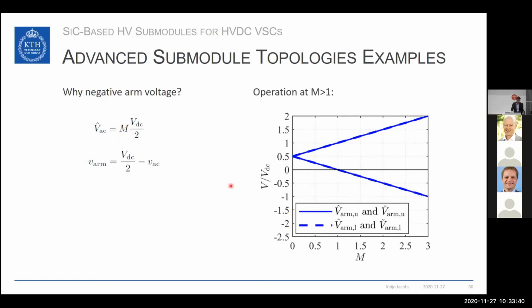On the y-axis, you have the voltage normalized to the DC voltage, and on the x-axis, you have the modulation index. The different curves represent the maximum and minimum voltage that has to be provided by the converter arm, plotted for both the upper and the lower arm. As you can see, for a design with a modulation index lower than 1, we have only positive voltage. If we run the converter at a modulation index higher than 1, we need to design the arm with negative voltage, thus submodules with negative voltage are required.